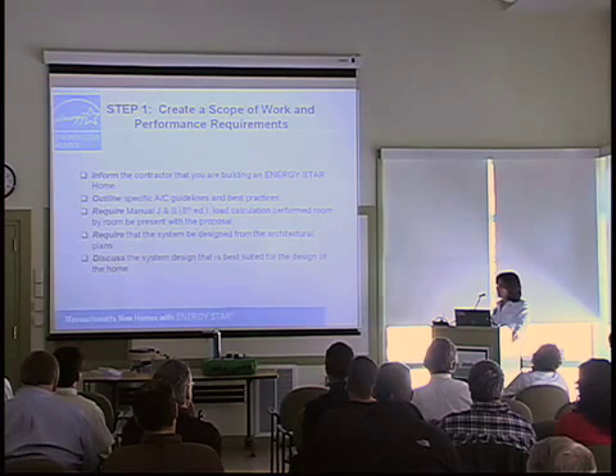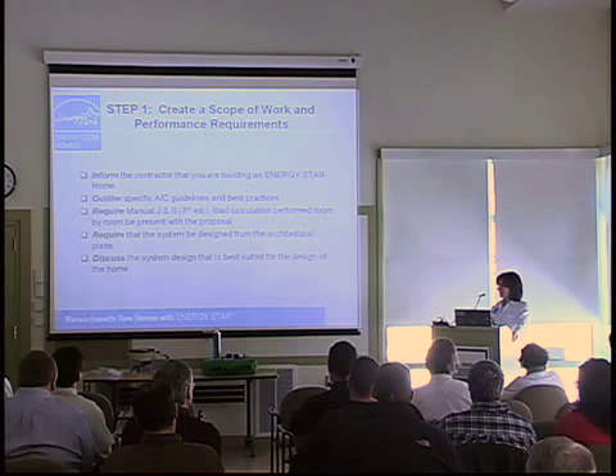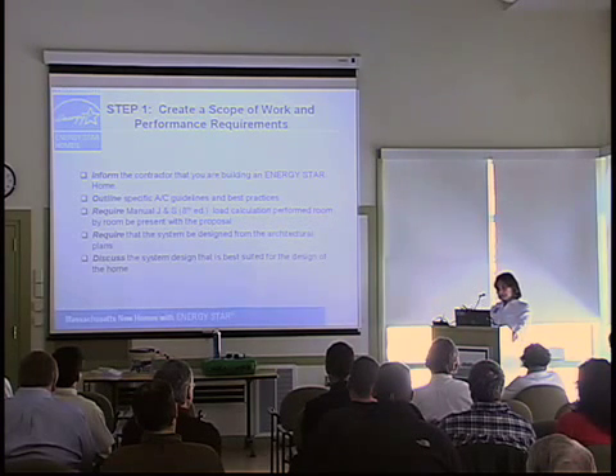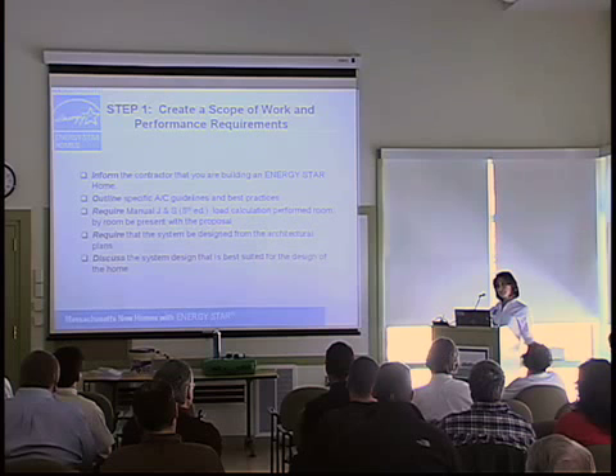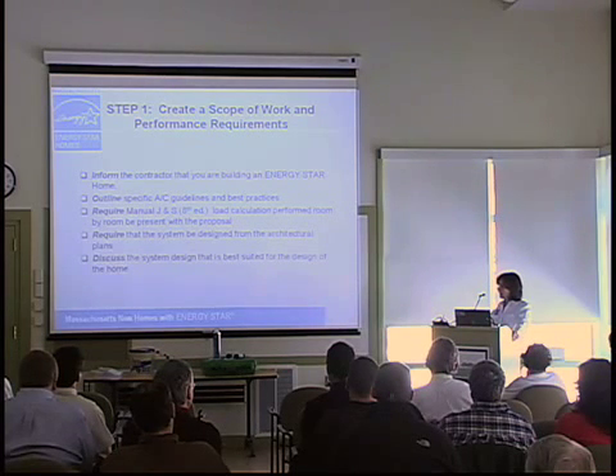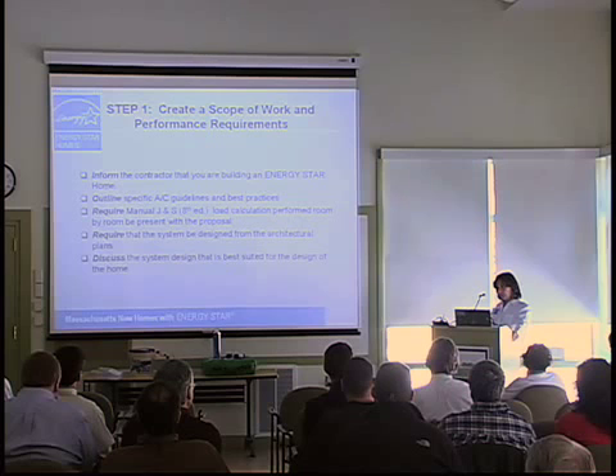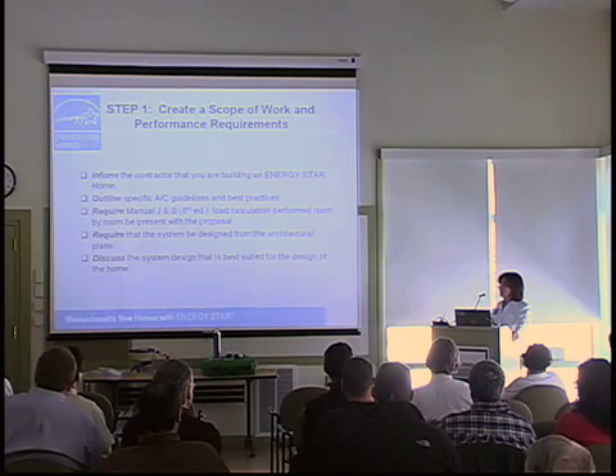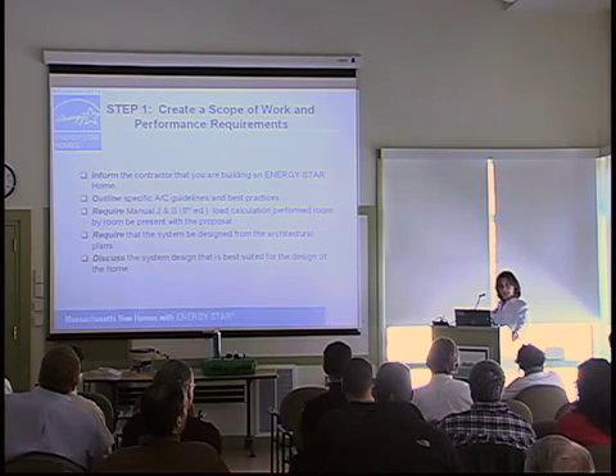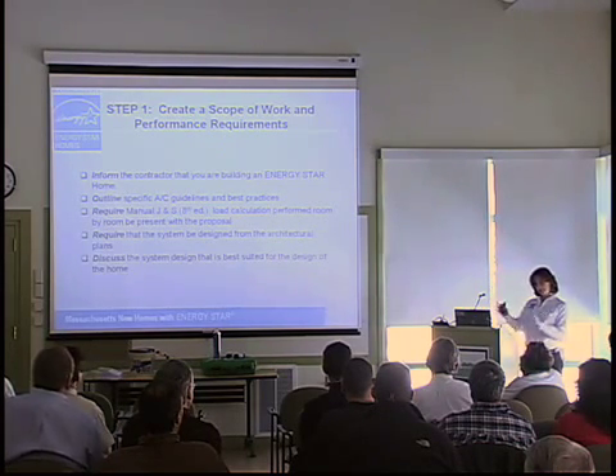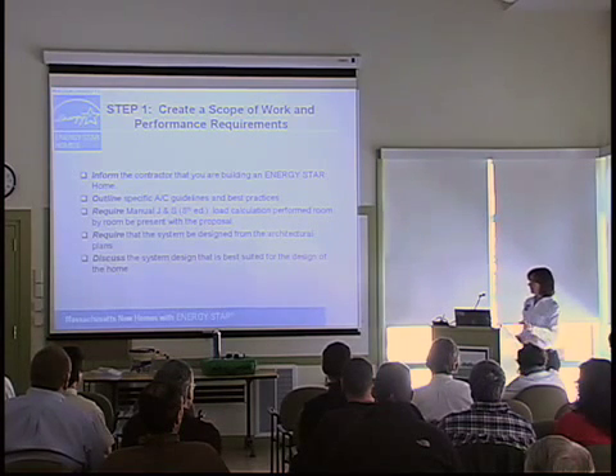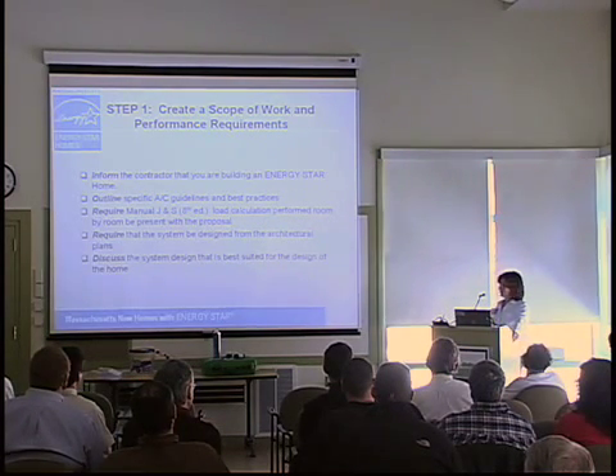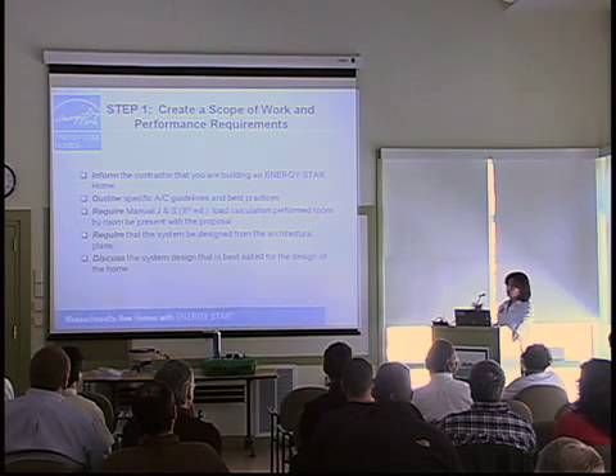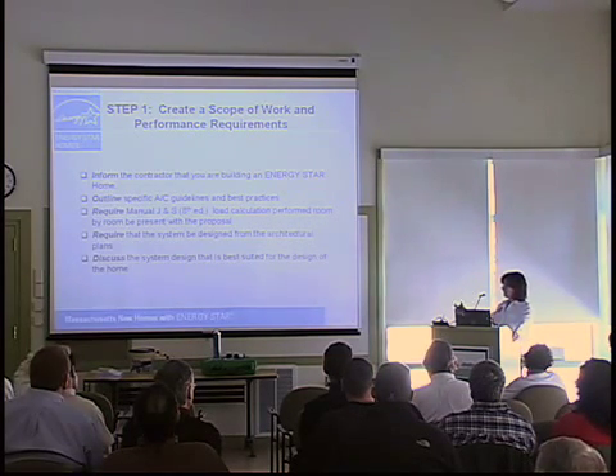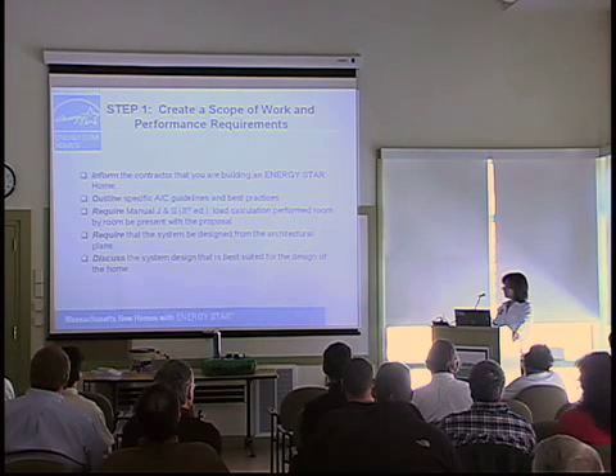So, put some thought into the type of system you want, discuss the design that you're thinking of, and take some time to actually review the floor plan with the contractor and look at your options for zoning. On larger houses, probably 4,000 square feet and above, you're probably going to start looking into a hydro air system where you have a number of systems that are going to be operating and could quite possibly give you some energy efficiency control with which ones are running at full capacity and which ones are not.